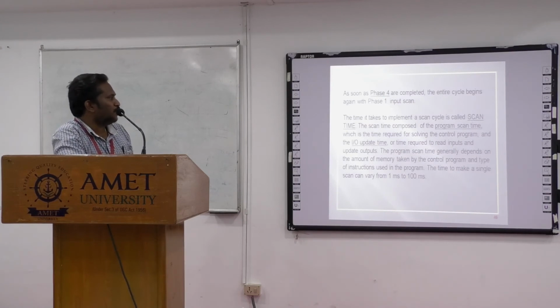The time it takes to implement a scan cycle is called scan time. The scan time is composed of program scan time, which is the time required for solving the control program, and the I/O update time, or time required to read inputs and update outputs. The program scan time generally depends on the amount of memory taken by the control program and the type of instructions used in the program. The time to make a single scan varies from 1 millisecond to 100 milliseconds.